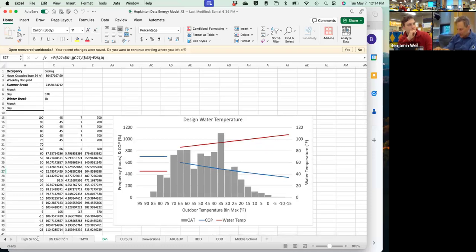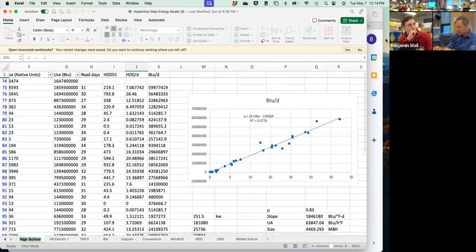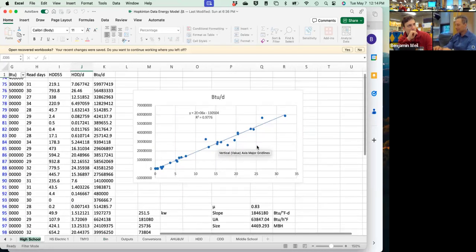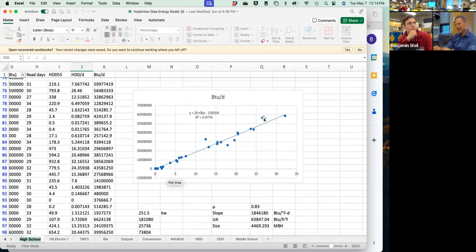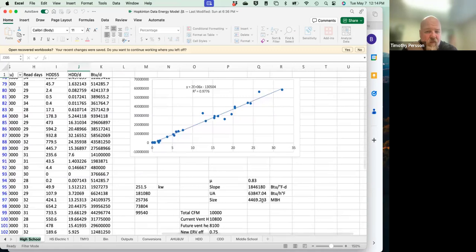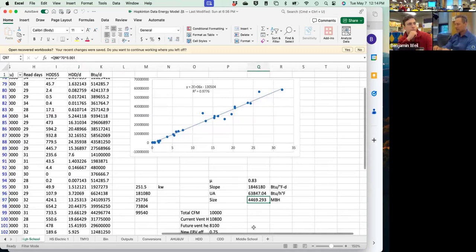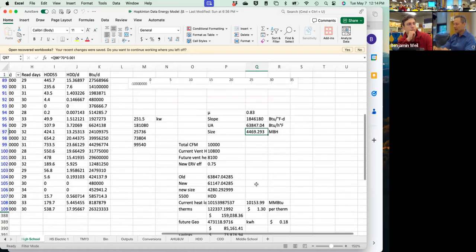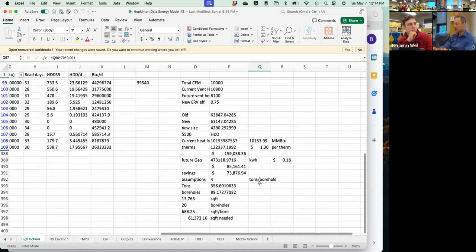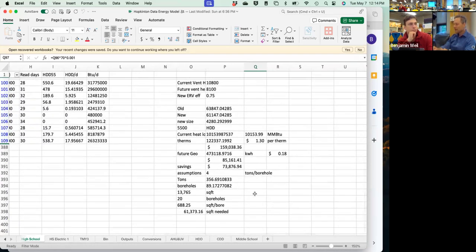So, see this. Yeah, so this is our model right there. And what we can say is that is a pretty good line. And what it allows us to do is size the required heat output based on what you actually have. And then from that, we've made an assumption about the heat output of boreholes. And those are 500-foot boreholes. You may have had someone recommend to you 200-foot boreholes.